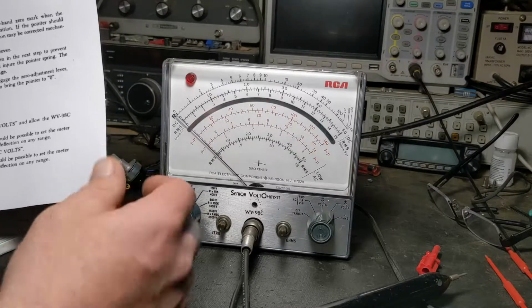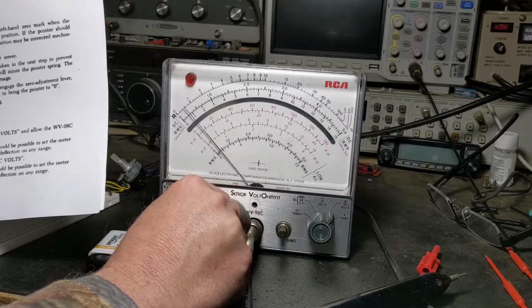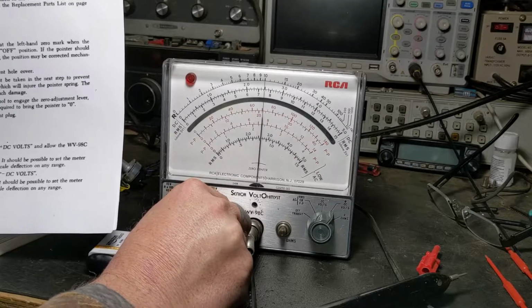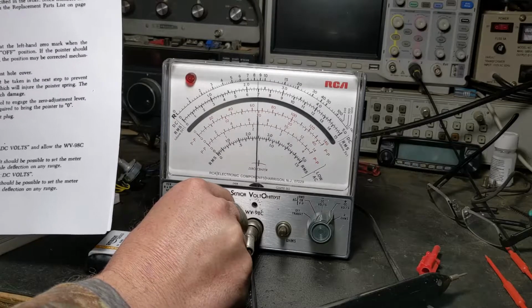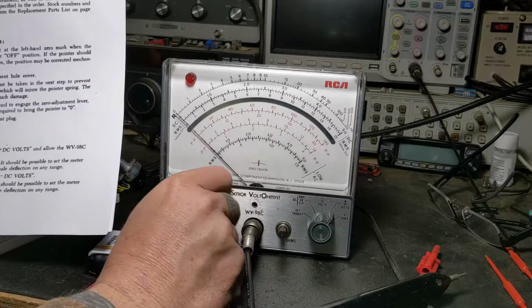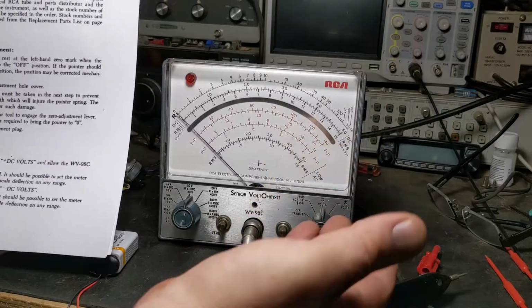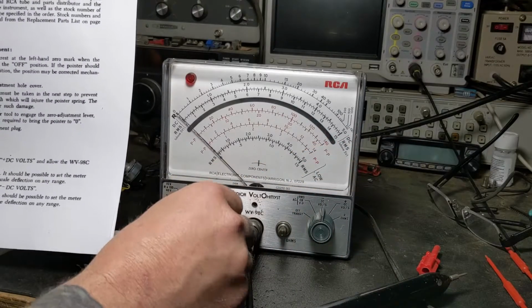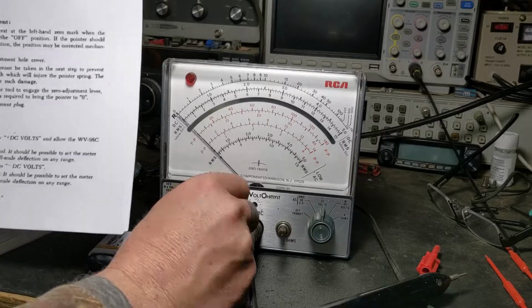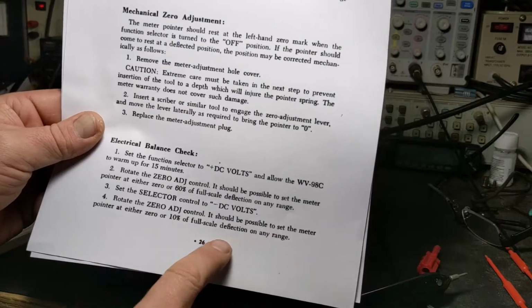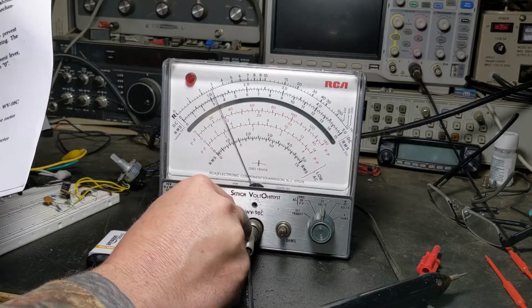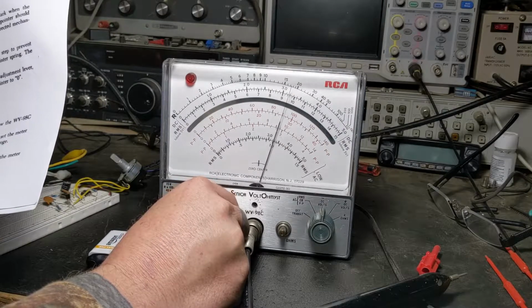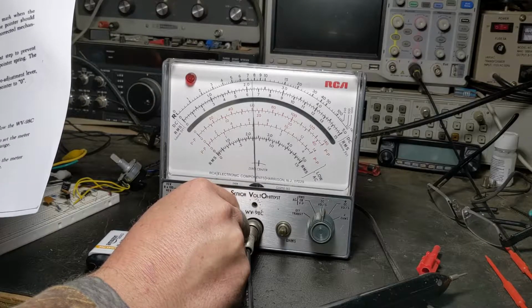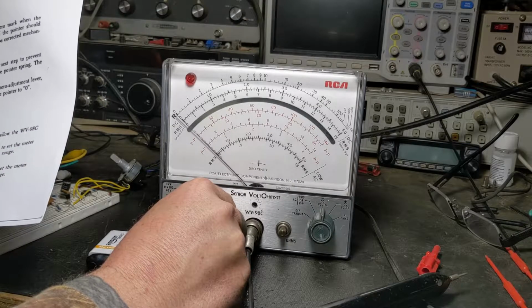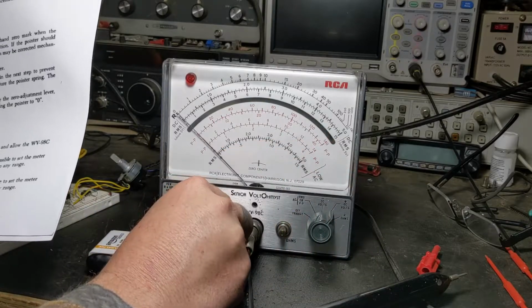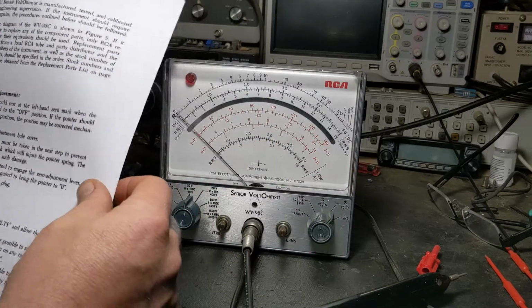That one 15 minutes. I don't know why I had it on the 15 volts range, but anyway, what they're saying is you should be able to go at least 60%. So there's about 50, 60, 70, 80, or almost. So that's not bad. Go back to 50 here, and then on the DC, on the negative DC volts, you should be able to run the 0 at least 10% of the full scale deflection. So it should be able to go way past 10%. And this is about 60 is where that's going to go. And put it back there. I'll 0 that in a minute.